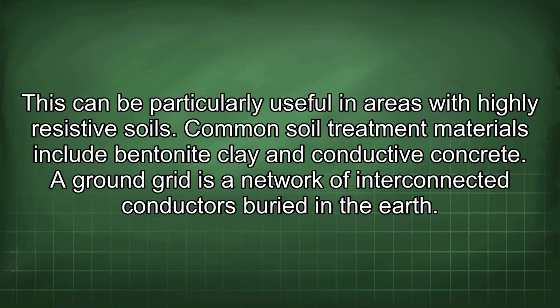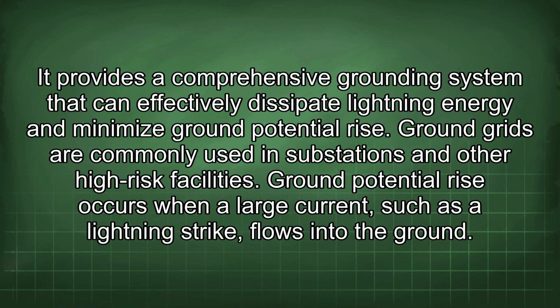A ground grid is a network of interconnected conductors buried in the earth. It provides a comprehensive grounding system that can effectively dissipate lightning energy and minimize ground potential rise. Ground grids are commonly used in substations and other high-risk facilities.